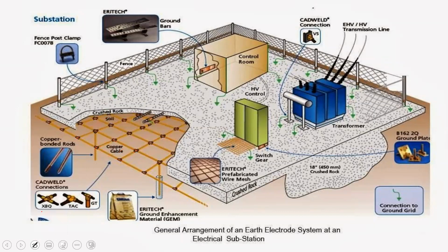Thirdly, you have some rods here. You see these rods? Well, they only show two here, but obviously there'll be more. You can increase the number of rods. So those are your vertical rods here. You can increase the number of meshes, so you'd use more wire. And you can make the grid itself deeper.